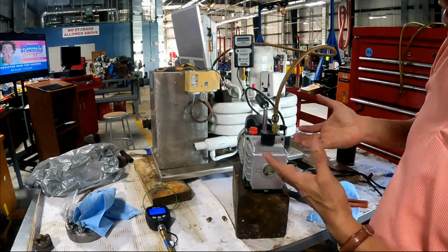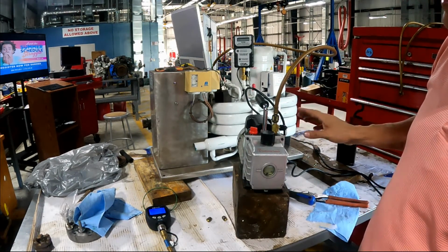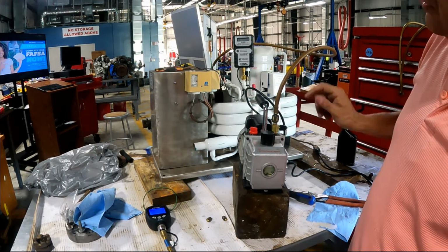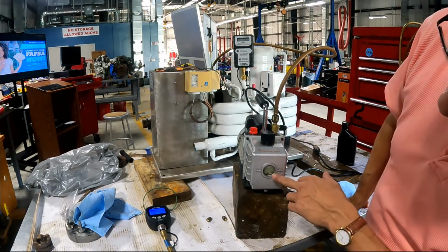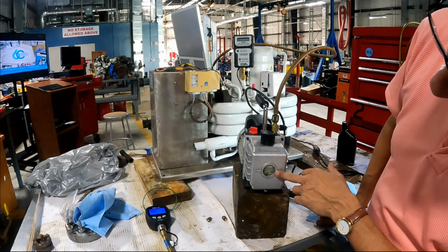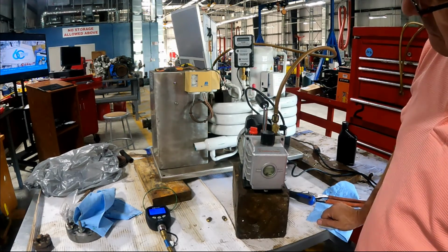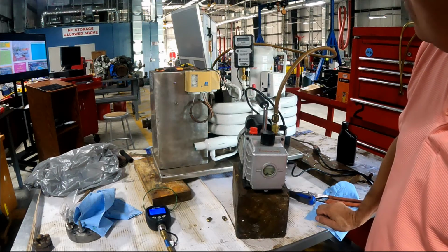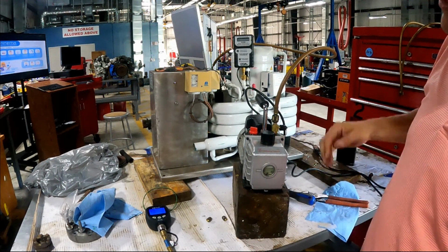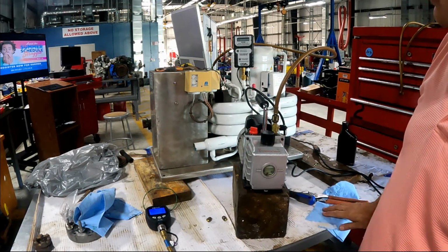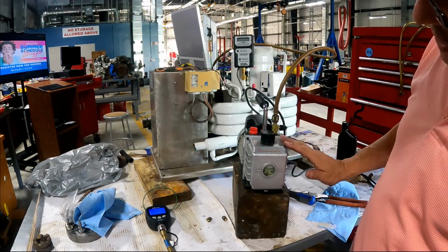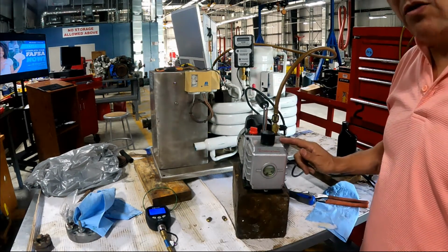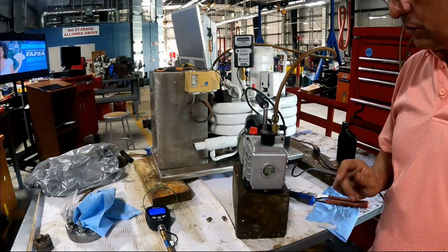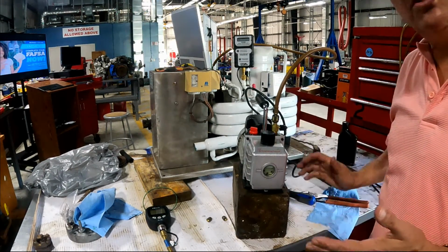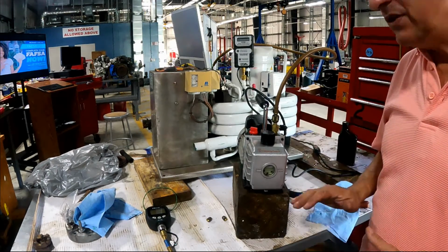That white vapor is humidity. Humidity going out. I found a lot of water when I recovered the freon in this unit. You see, the oil is foaming. This is an indication of a lot of humidity in the system. But the system starts to stabilize slowly until the majority of the humidity is removed. Remember, the function of the vacuum pump is to remove moisture. Normally that process takes 40 minutes, 45 minutes. It's a long process until the system is completely empty of moisture.